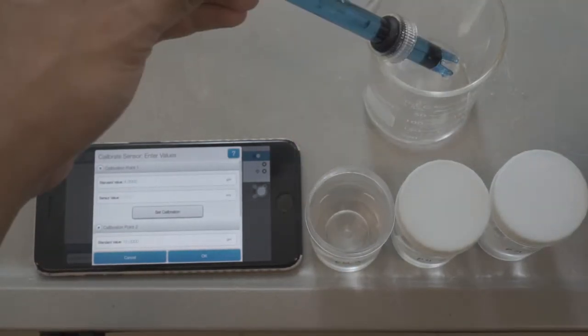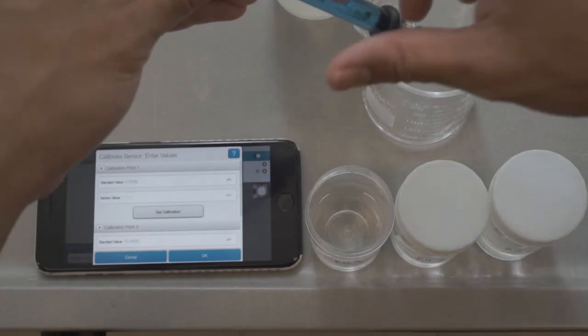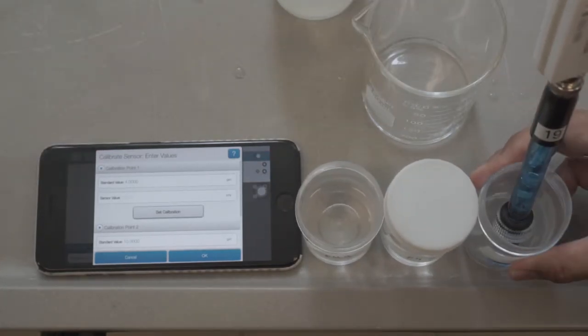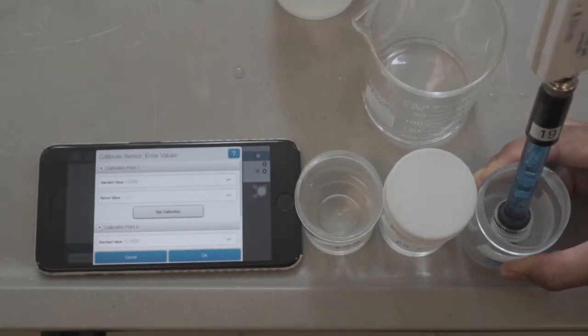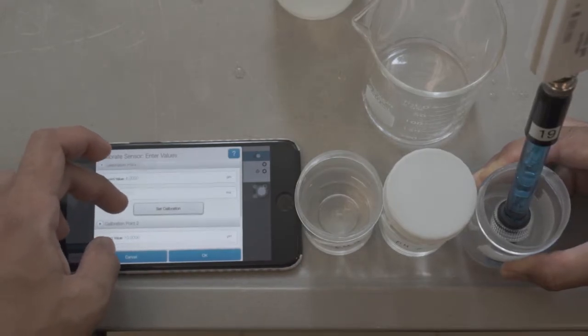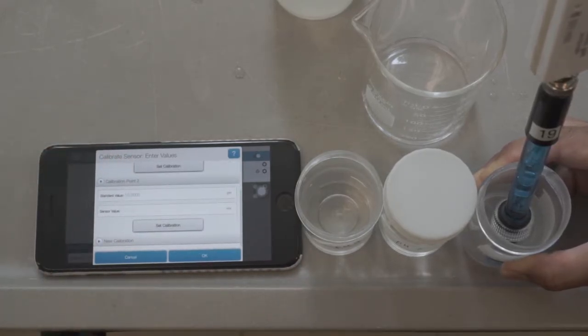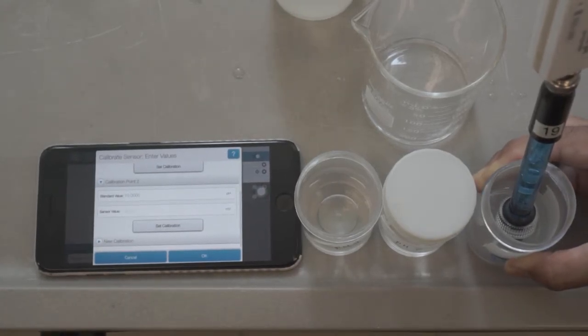Rinse the end of the probe with distilled water again. Dip the end of the probe into the pH 10 solution. Scroll down to Calibration Point 2. Once again, keep a close eye on the sensor value. Once the sensor value has stabilized, press Set Calibration.